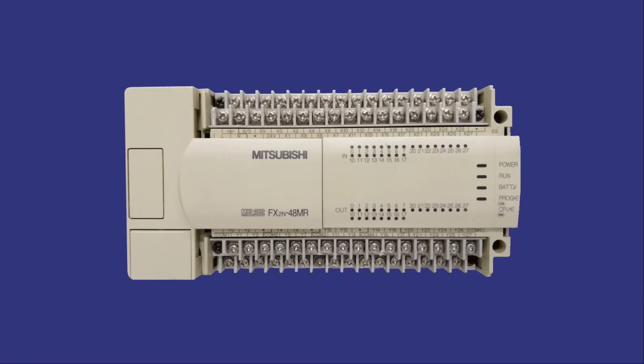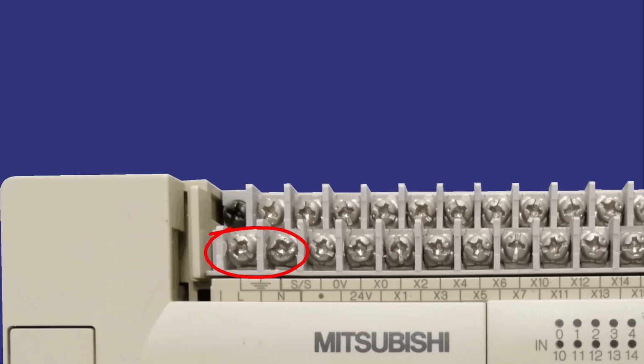This is Mitsubishi FX series PLC. It has 24 digital inputs and 24 relay outputs. Voltage supply is AC 110 to 220 volts. Looking closer at the terminal, these two terminals, L and N, are for power supply. Here, you can connect your AC power supply.